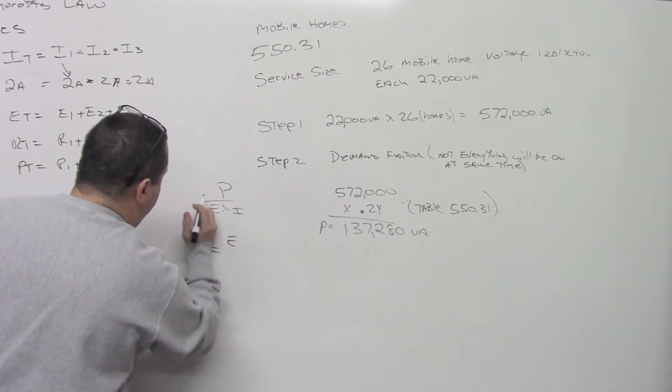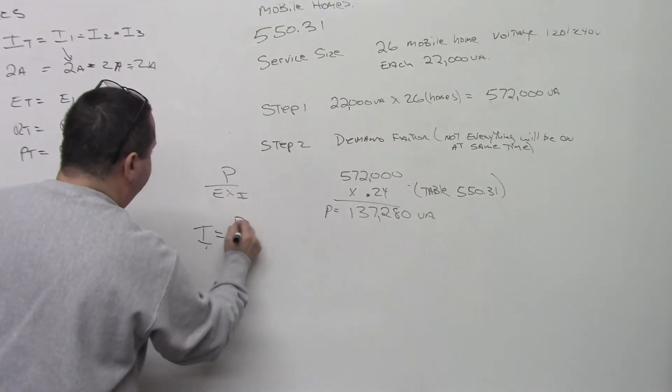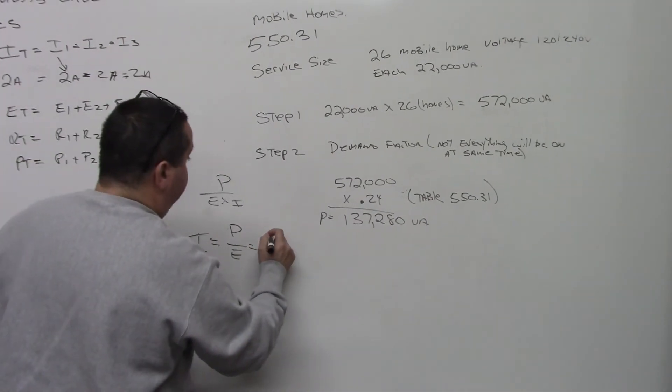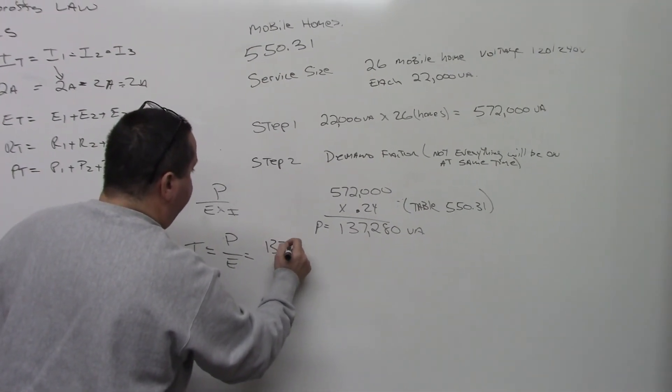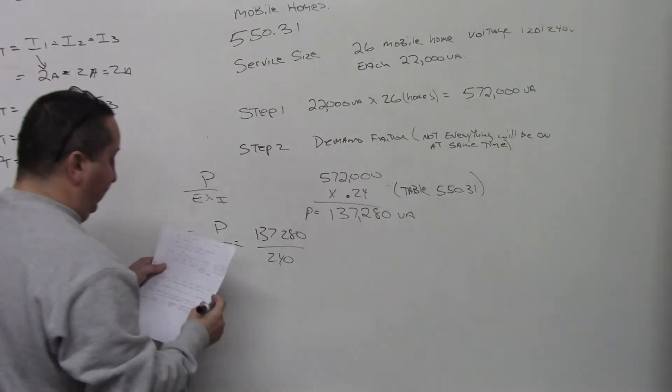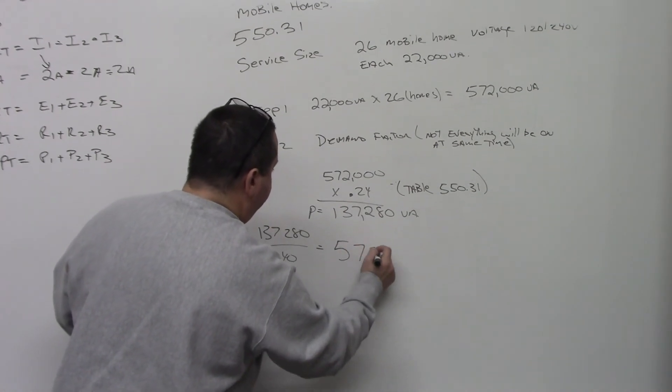So we're going to go, I equals P divided by E, which equals 137,280 divided by 240. And if you do this, you're going to come out with 572 amps.